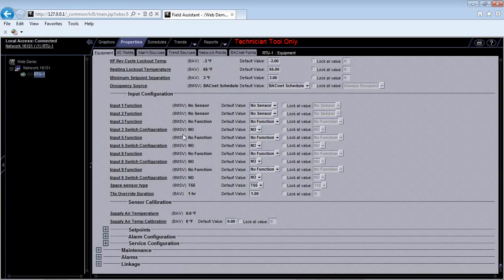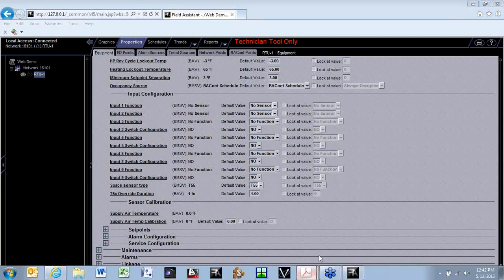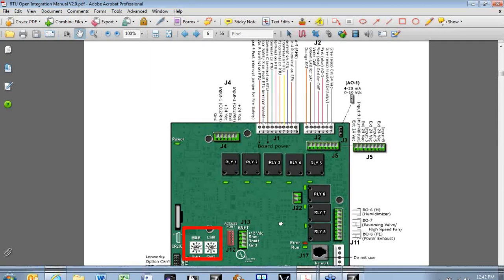The last thing in unit configuration is the space sensor type. These RTU Opens can take 3 space temperature sensors, right? And if we look at them, we've got a T55, a T56, and an SPT sensor. A T55 is just a 2-wire thermistor sensor. Has to be a 10K Type 2 thermistor, wires directly into the RTU Open on 2 terminals. Okay, I think we can look at it here on the install or the integration.